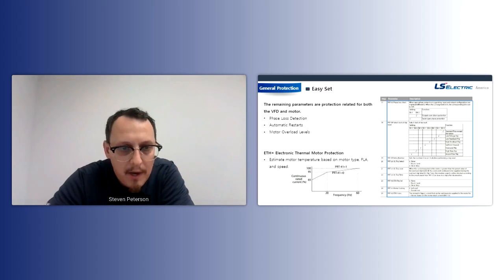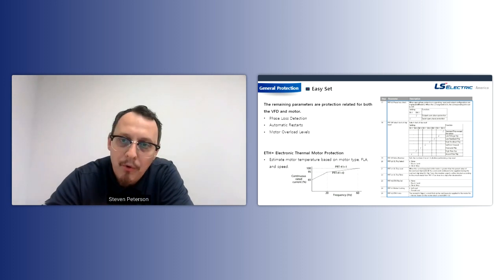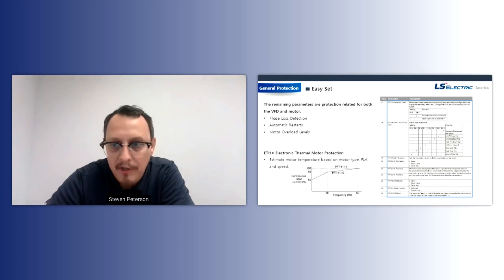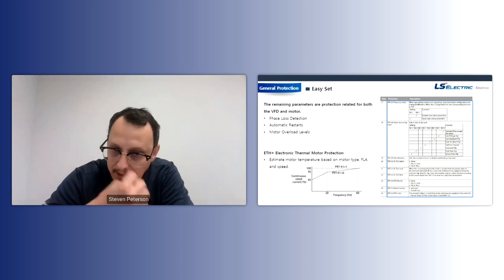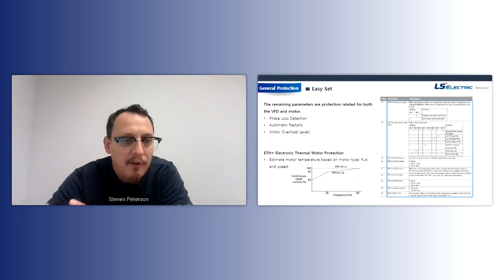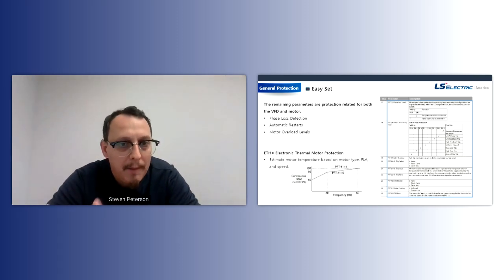So this is actually for a motor electronic thermal protection. And what it does is, as we mentioned, we have the previously programmed motor current, which says, hey, if we go over our motor current, we're going to trip you out after a certain time. What this does is it looks at motor current, but it also looks at motor speed as well. So a lot of motors in this industry, just like pumping in general, are going to be self-cooled. So that means the fan is coupled onto the back of the motor shaft. So if you slow down the motor, well, then you slow down the cooling effect of the fan coupled to the motor shaft. So you can only run so slow before the motor starts to heat up.